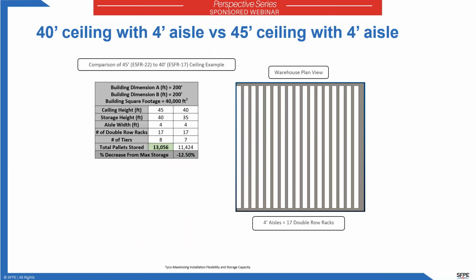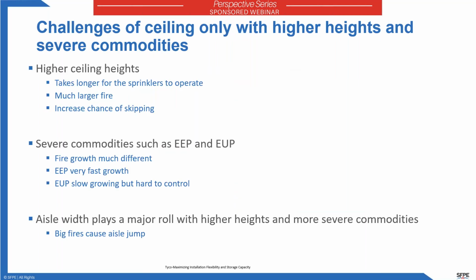So let's compare the 40-foot ceiling with the 45-foot ceiling. Again, this is where everyone has essentially the same approved sprinklers with the 4-foot aisle width. You can see there's a significant increase in the amount of capacity just by adding the extra tier within this space. So about 13,000 pallets could be stored in this space. However, as I noted, once you get above 45-foot ceilings, things change.